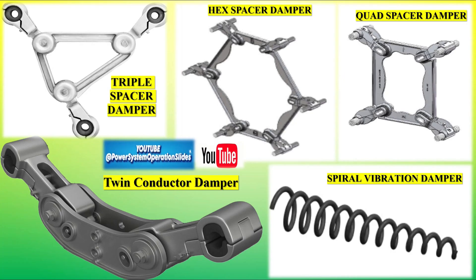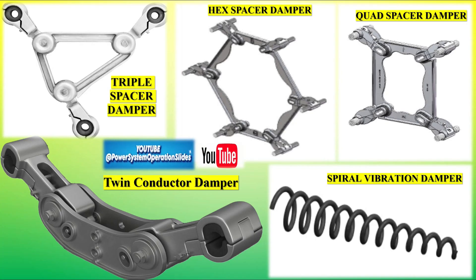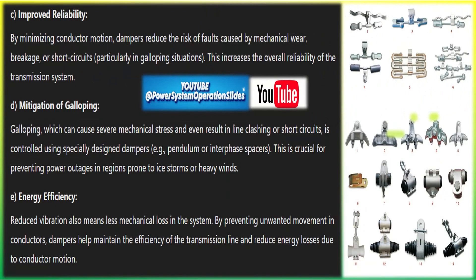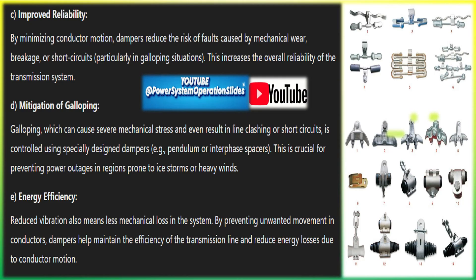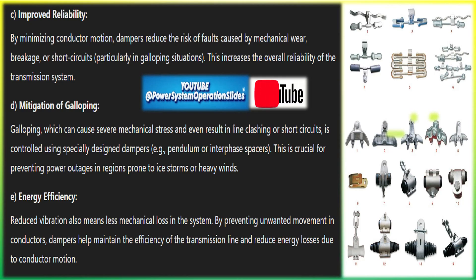Interphase spacers are used between phase conductors in areas where galloping is a concern. These are mechanical devices installed between conductors of different phases to prevent phase-to-phase contact during galloping. The spacers physically separate the conductors and absorb some of the energy from galloping, reducing the risk of faults or conductor clashing. They are commonly used in areas with severe icing or galloping risk.